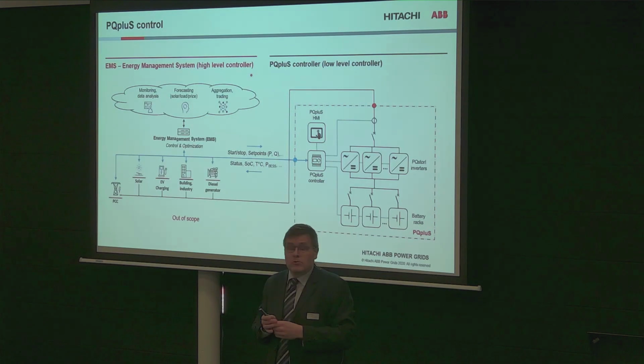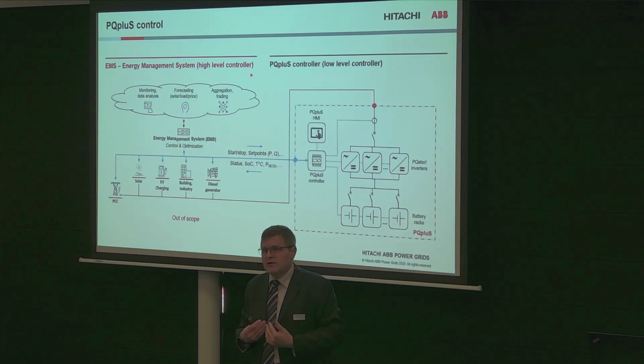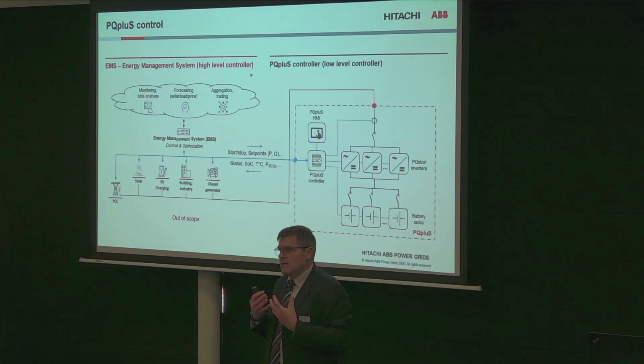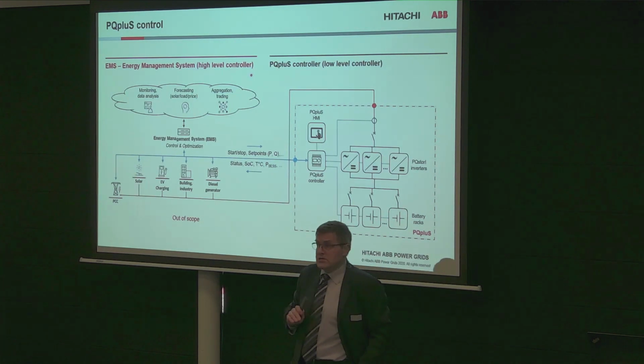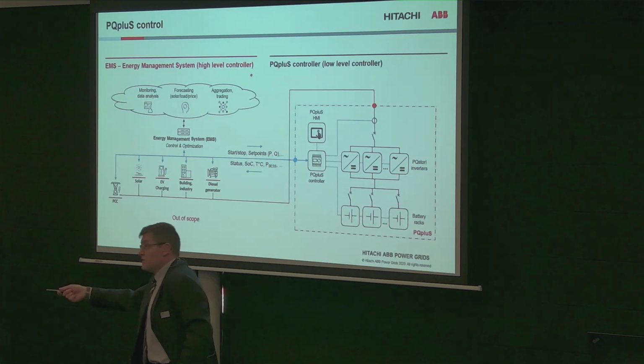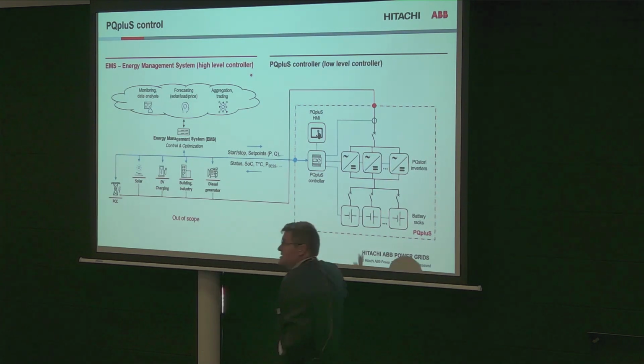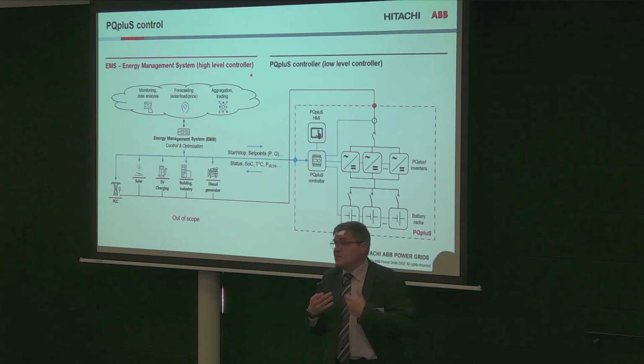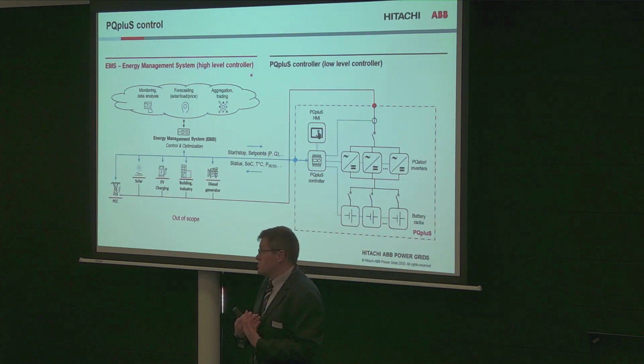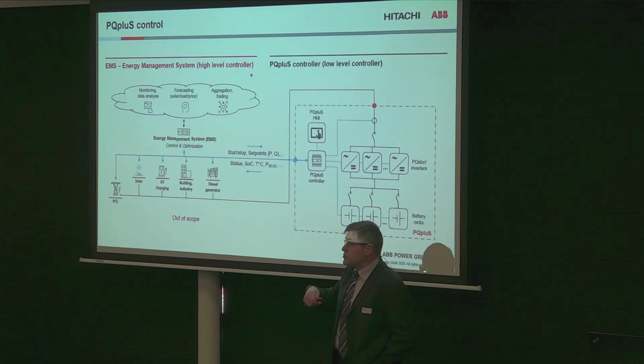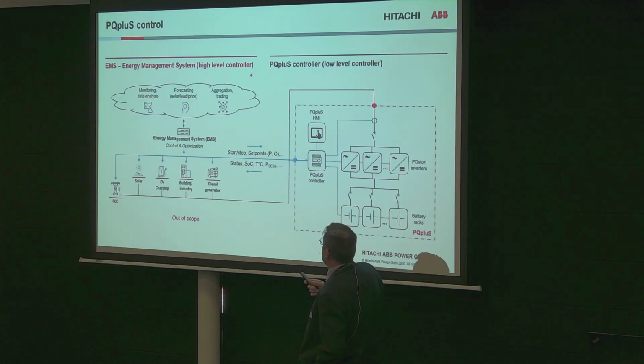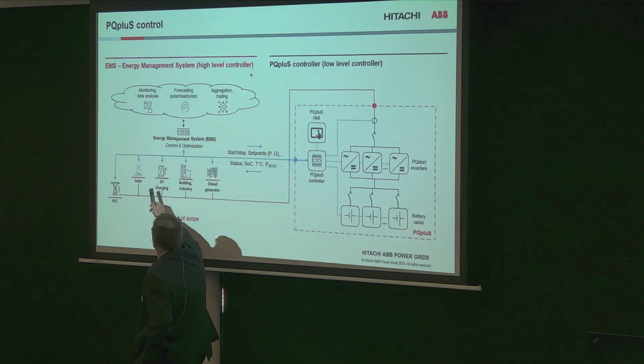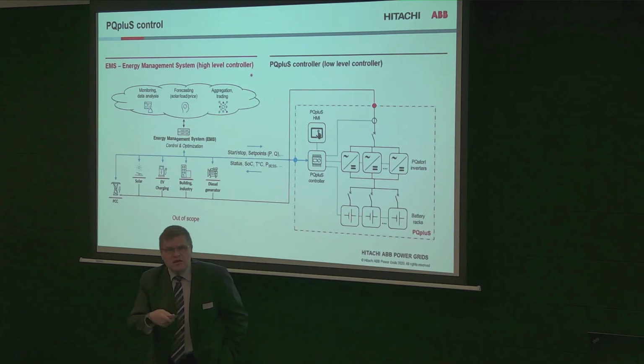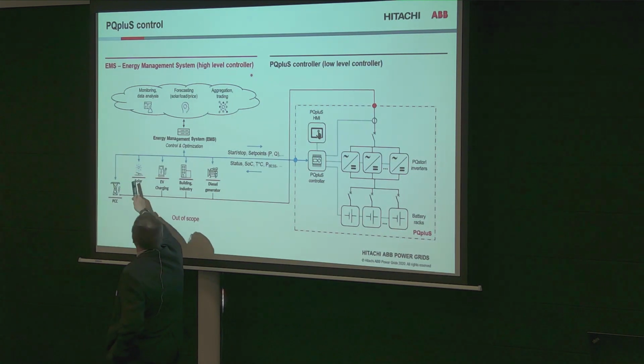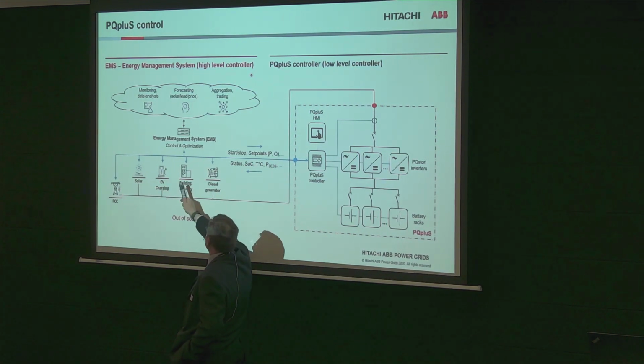Hitachi Energy can provide it. It's not from our factory, but we need a system which tells the battery energy storage system to charge the battery or discharge. So our system will not by default decide by itself to charge or discharge my battery. No, this is coming from a system. We can also do power factor correction, so we can inject reactive energy as well. And this system will interface with the connection with the grid to do peak shaving, or to optimize the current here, with solar and electric vehicle charging.